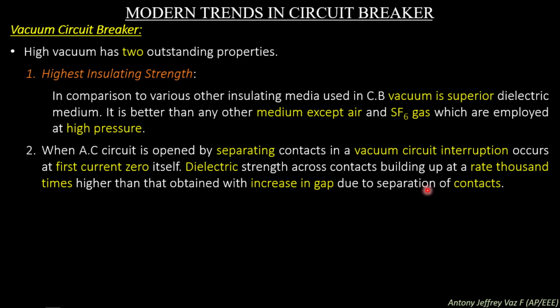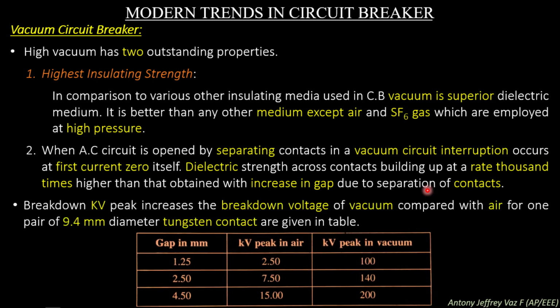So in vacuum circuit breakers, the length of contact separation required is lesser because the medium is not present. So arc formation in a medium is not present. So the arc is going to happen in a vacuum. So the length of separation of the contacts can be made minimum so that the arc can be extinguished by a vacuum circuit breaker with a shorter arc time.